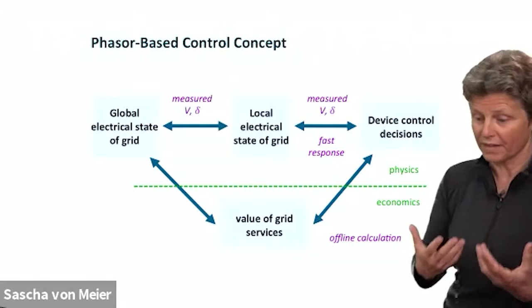The idea here is, instead of measuring frequency, which is kind of a global system-wide metric for power balance, we're measuring these voltage phase angles, which are a local measurement that corresponds to power flow locally on the grid. So the device control decisions are made directly in response to these measured quantities, which means you don't have to wait for people to compute a lot of things. You're making these fast decisions entirely in the realm of physics. And the idea is that the economics of who needs to get paid how much money for doing this can be taken offline and done more slowly, so that everything the devices do, in effect, could be thought of as an ancillary service of being available to perform this response.